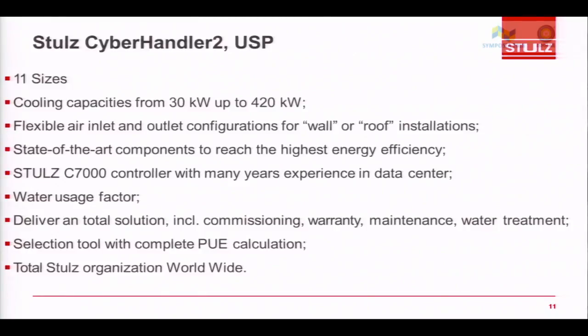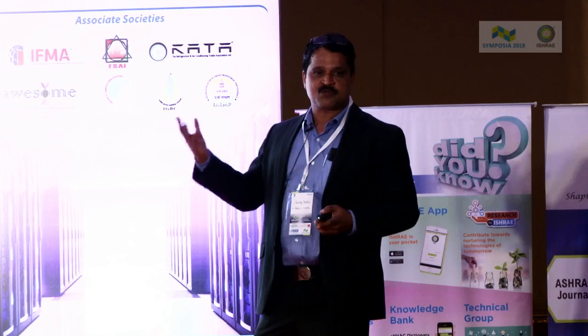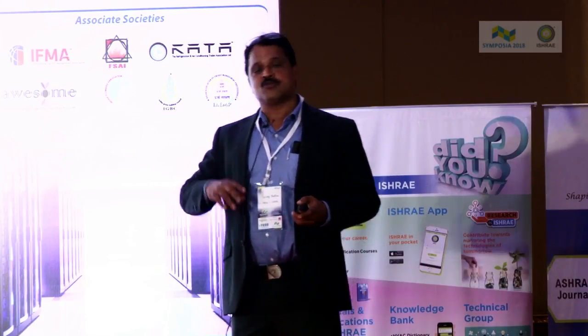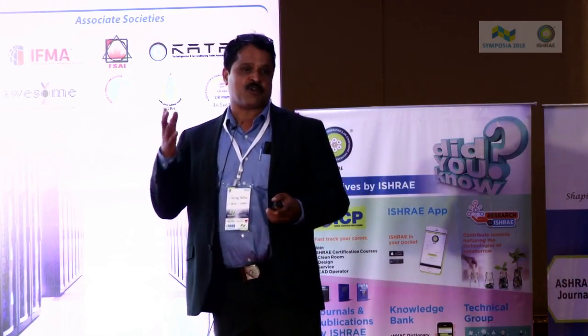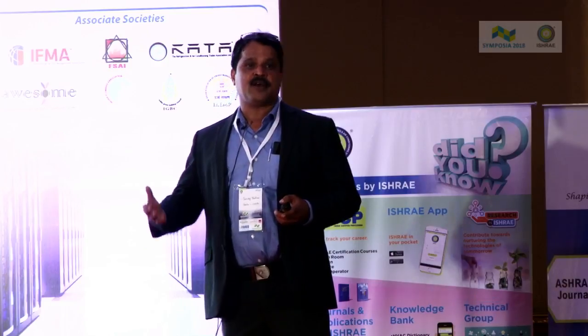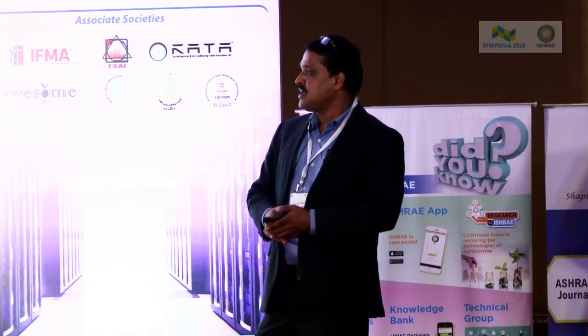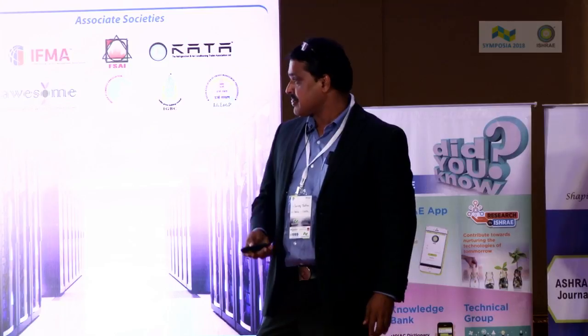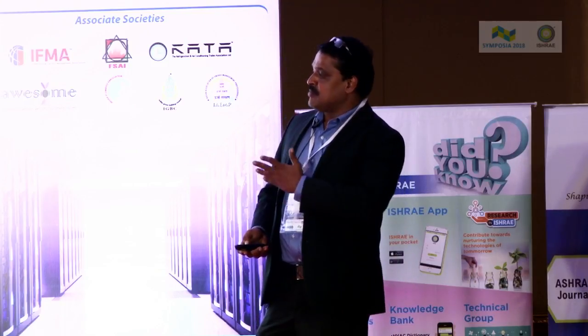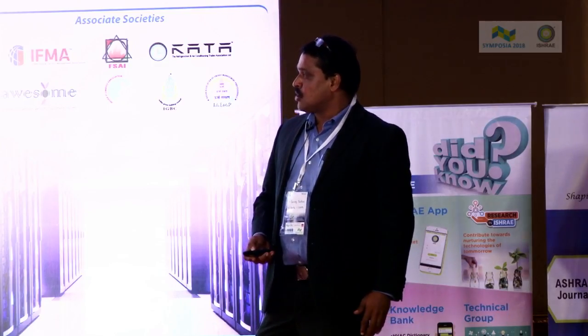My slide will cover what the water consumption will be when you do adiabatic cooling at such a huge capacity. For 100 kilowatt, how much water consumption will happen? Again, don't use bad quality water. Use an RO plant, use good quality water, and get the best efficiency out of it. Also ensure that your air to air heat exchanger doesn't get clogged and lose its efficiency. We have a complete selection tool, a total Stulz organization worldwide.